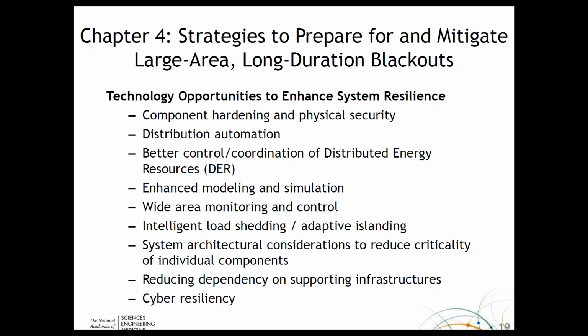Quite a bit was written in the report on intelligent load shedding, including demand response and those technologies, but more importantly, how they could be organized into something we call adaptive islanding. The way the system is operated today, the goal is to maintain the integrity of the interconnection and preserve the system as a whole through under-frequency load shedding or similar measures.